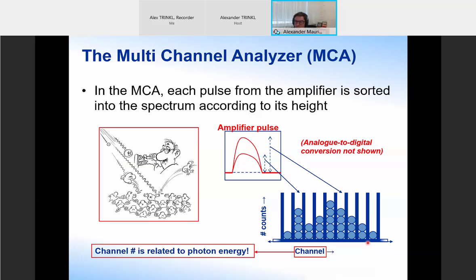In our histogram, that is our spectrum, we can then later relate to the photon energy of the incoming radiation by this proportionality that is kept throughout the whole signal processing. So the spectrum is simply a histogram of energy signals that have been sorted according to their amplitudes or heights into the appropriate channels. And of course, once we measure over time and for long enough, we'll start to see these characteristic effects in the spectrum, such as the peaks. But this is basically what the spectrum is: the plot of counts versus energy, as sorted events from energies deposited in our detector.